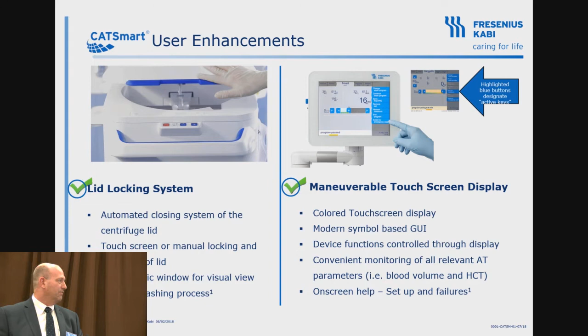We also added hematocrit sensors. So it has an incoming hematocrit sensor and an outgoing hematocrit sensor, so then you can see that the device is concentrating and doing what it's supposed to do. The first question I get as a perfusionist is, can we use this for quality control? They are not validated for that at this point. I can tell you that they are very accurate, but you have to understand what they're doing to use them if you want to validate them yourself. But I have to say it is just a monitoring device at this point.